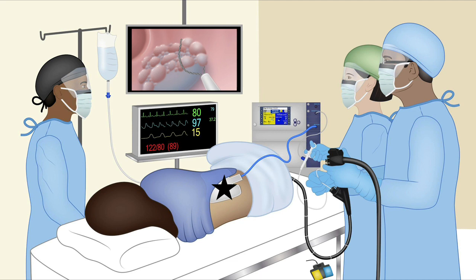What are the do's and don'ts about placing a dispersive pad? One, you should avoid placing it close to a pacemaker or a defibrillator or any other electrical generator. That's very important to do. Number two, avoid placing it over a tattoo. Avoid placing it over a very hairy area. Avoid placing it over a bony point. Avoid placing it over an artificial hip. These are some things one needs to keep in mind. You should pick up an area where there's a lot more muscle and put it over there. And also avoid putting it on a medication patch that is attached to the skin.